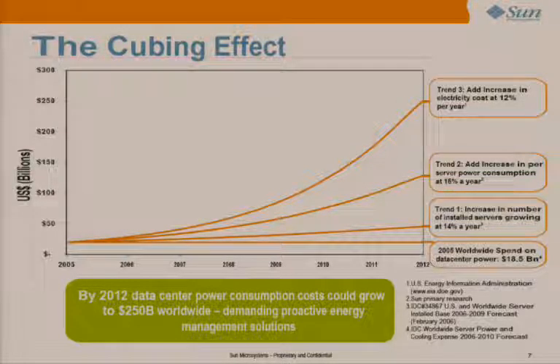Each generation of servers actually consumes more power than the generation it replaces. Why? Because the microprocessors got faster, there's more memory in the servers, there's more disk in the servers, the fans in the servers are more powerful, et cetera. I did a trending analysis of that, and it turns out that the average power draw of, let's say, a 1 rack unit high, 2 processor server increases at the rate of 16% per year, and this has been a steady trend over the past 9 years or so.